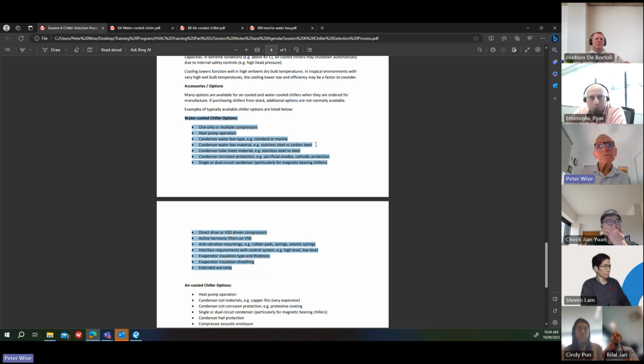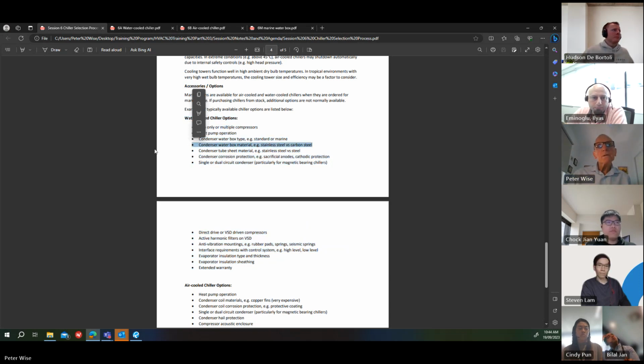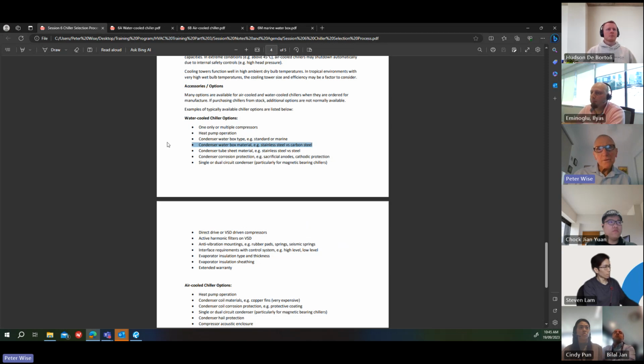Condenser water boxes, I'll just go through these one by one. Some manufacturers will offer you a stainless steel water box instead of a carbon steel. Again, you're talking a few $1,000s at least to go to stainless steel, but that might be worthwhile because it's an open system. The water boxes are subject to corrosion. If you use stainless steel, you don't have the same worries.